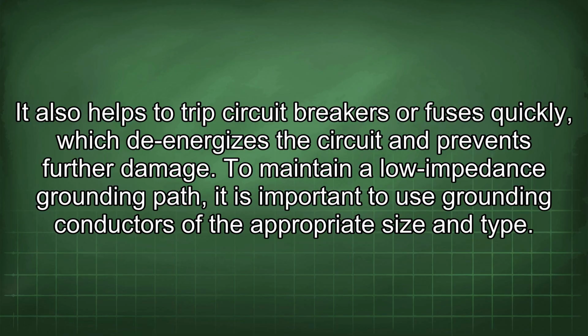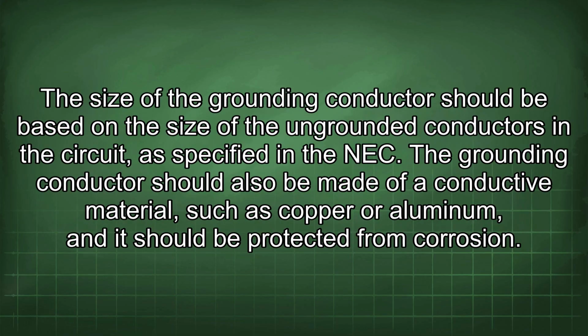To maintain a low impedance grounding path, it is important to use grounding conductors of the appropriate size and type. The size of the grounding conductor should be based on the size of the ungrounded conductors in the circuit, as specified in the NEC.